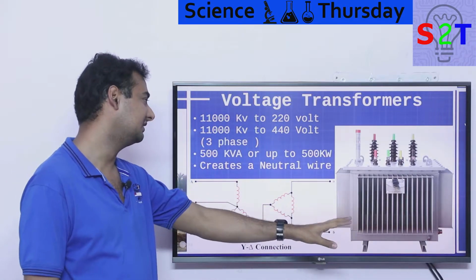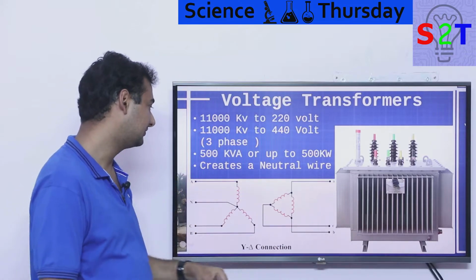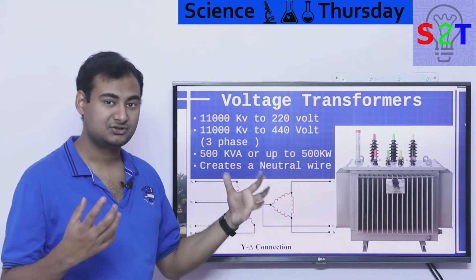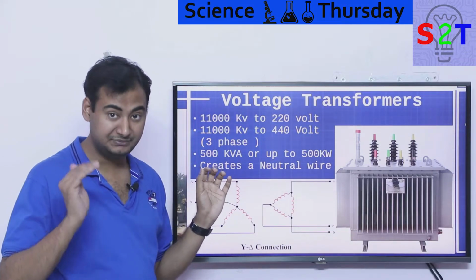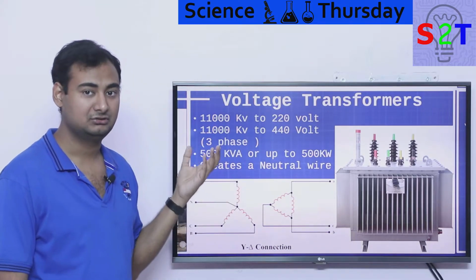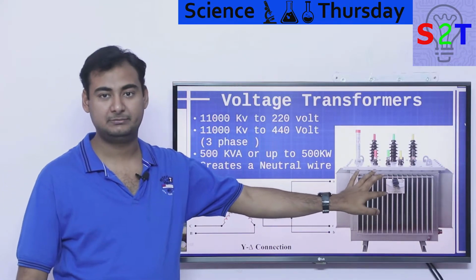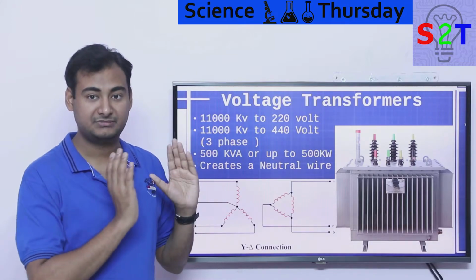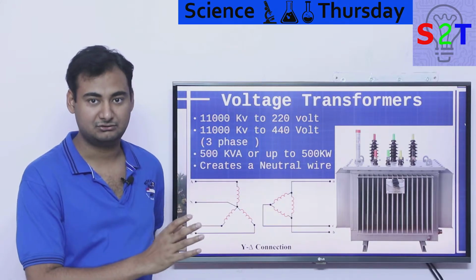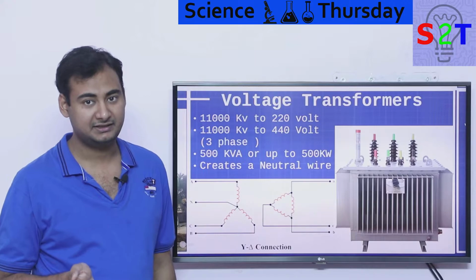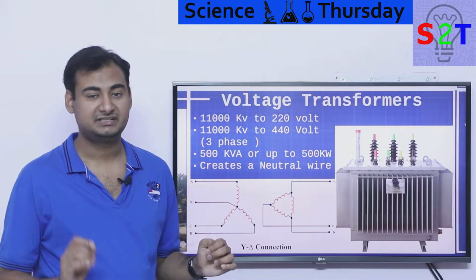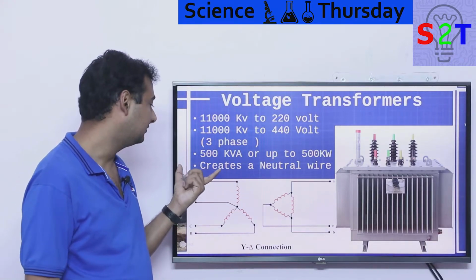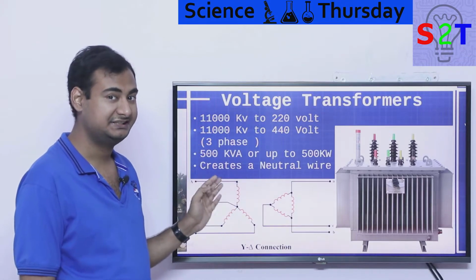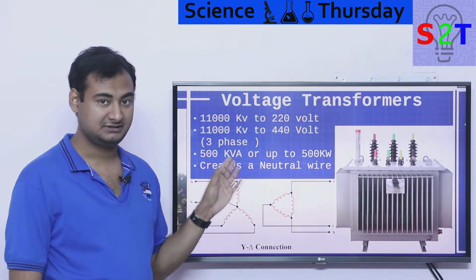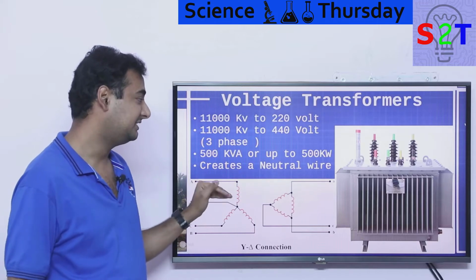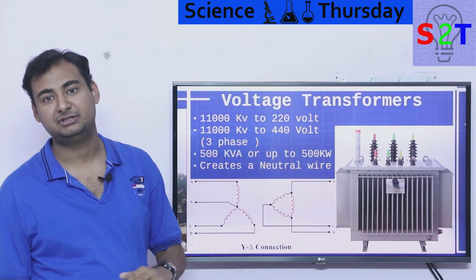Generally you will always see something like this, 11 kV to 440 volts. Now the upper rating in terms of how much power it can carry is generally below 500 kVA. There are generally steel plates, sometimes etched onto, bolted onto, or welded onto the transformer. You can easily read it. You will always find they mention their load in terms of kVA, kilovolt ampere. Now you have to understand this kVA is an upper limit. That means up to 500 kilowatt can be drawn from it.